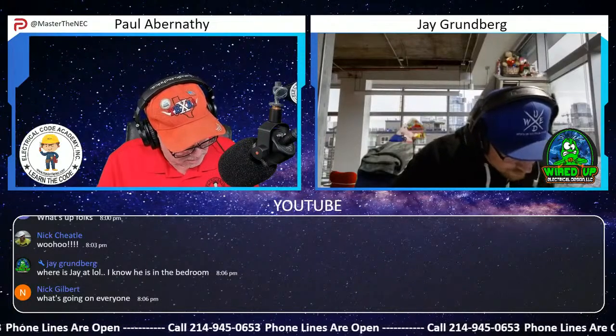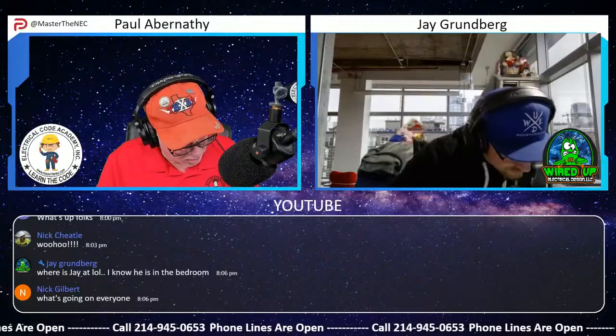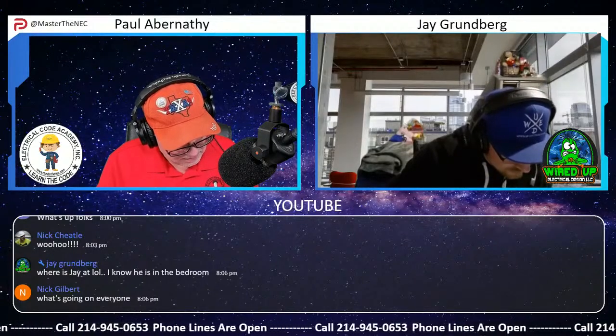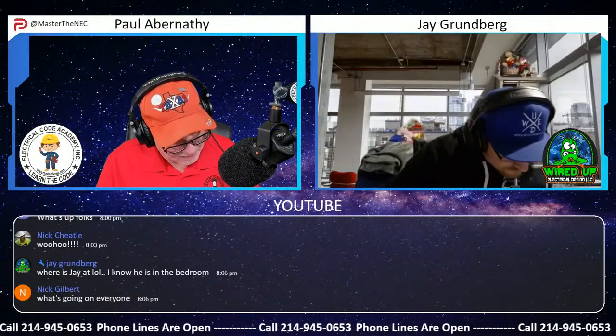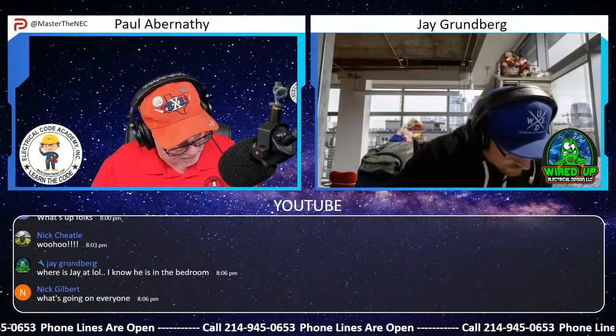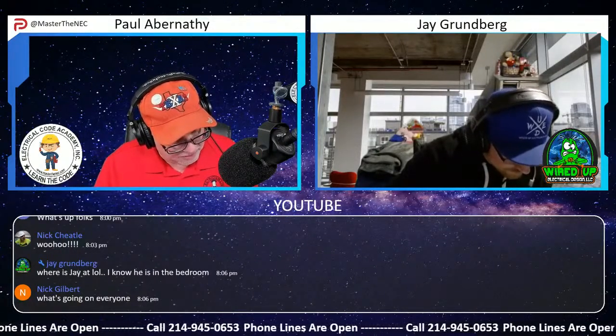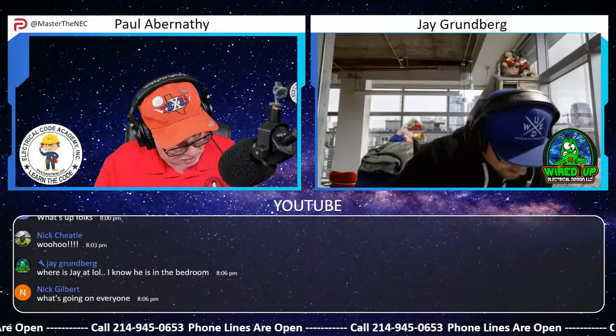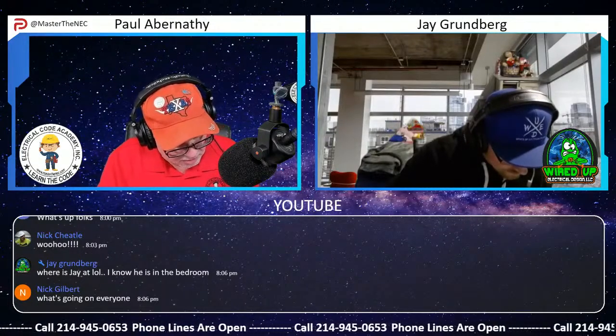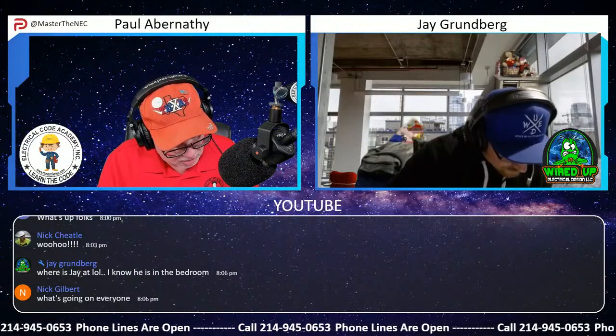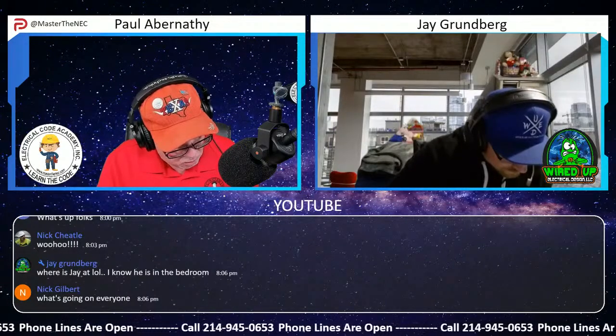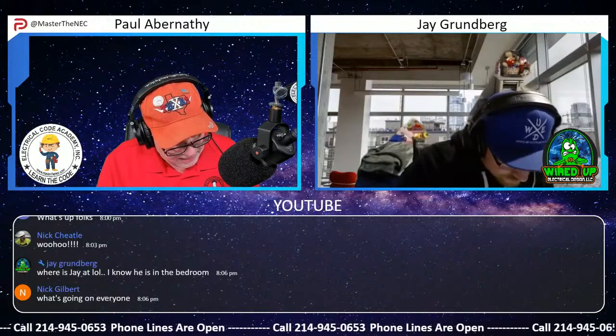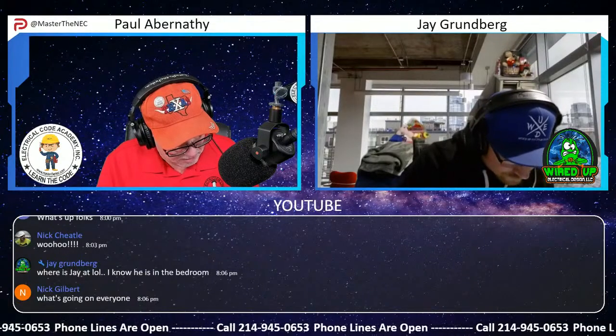348.20A2B. Is it part of a listed assembly? Yeah. I'm not sure, you'd need more context than this. So that is minimum size. FMC flexible metallic conduit less than metric designator 16, or trade size half, shall not be used unless permitted in 348.20A1 through A5. So this is an allowance for you to be able to use an FMC with a metric designator less than a half, giving you some allowances for when you might be able to utilize that.